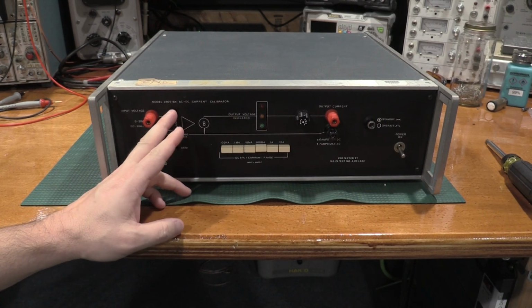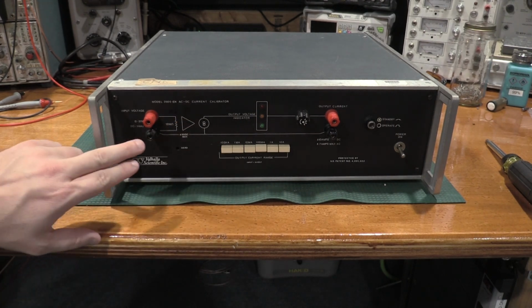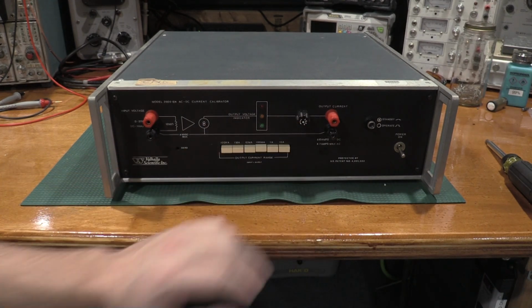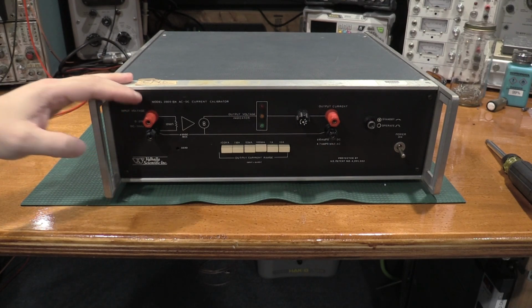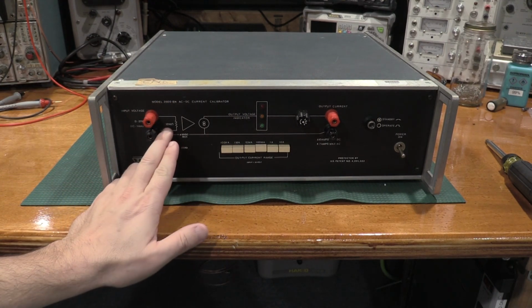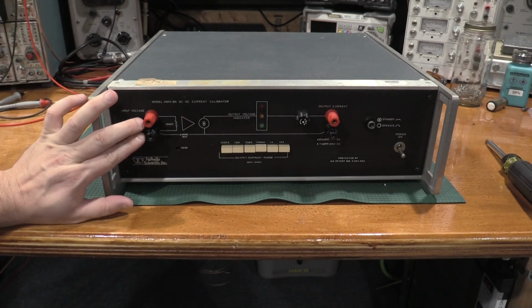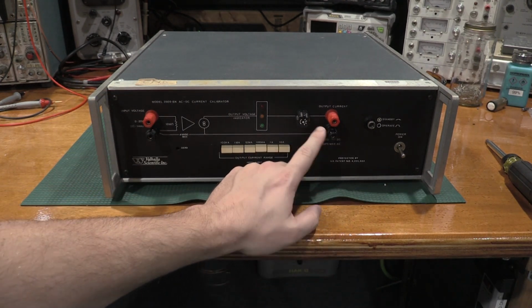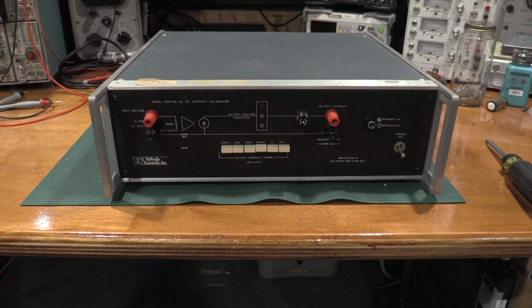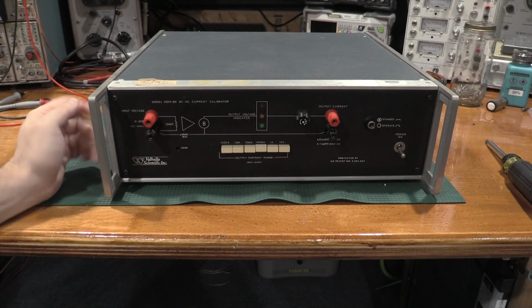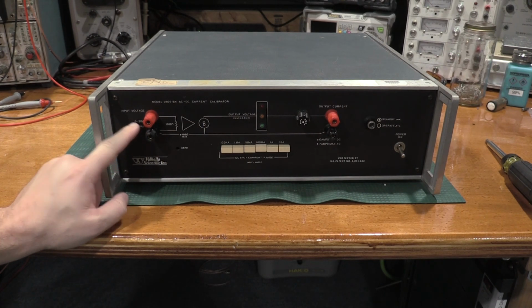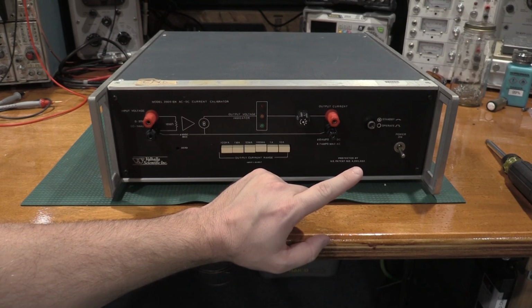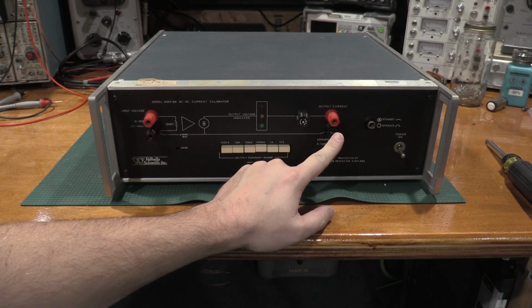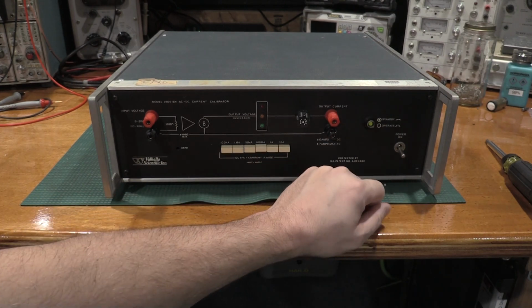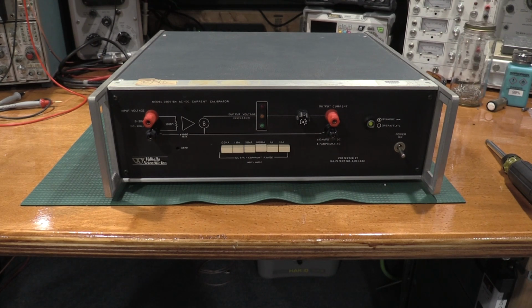So the main differences between the 2500E, EP, and EN are the input impedance, the compliance voltage, and the control voltage. On the E model, you have a 100 kilohm input impedance, a 0 to 1 volt control voltage, and a 10 amp full scale output for the current source. The compliance voltage on that one, I believe, also goes to 10 volts. On this one, we have a 0 to 20 volt control voltage, and I believe it's a 10 volt compliance voltage on this one. I'm not 100% sure, I'll have to check the documentation for that.